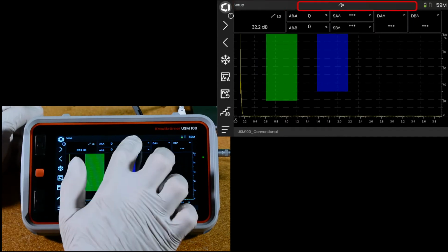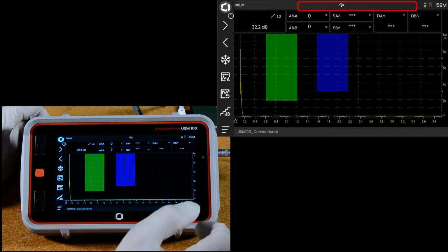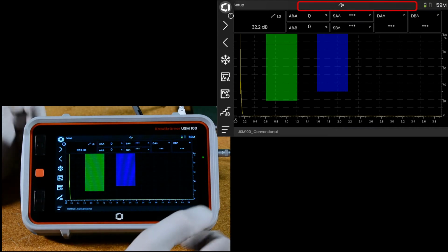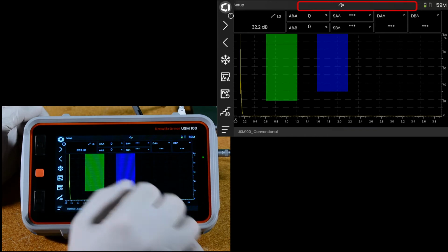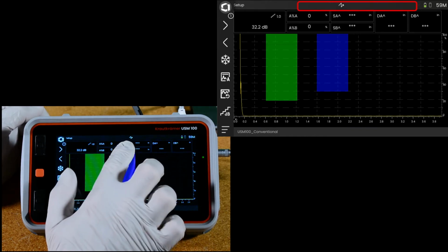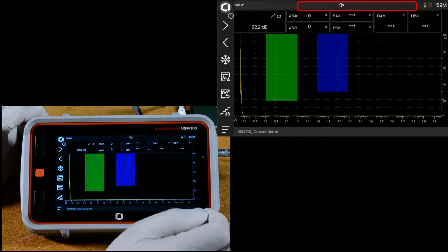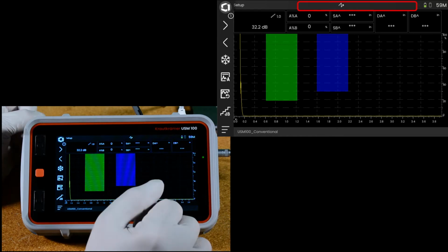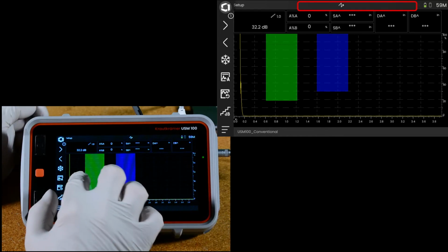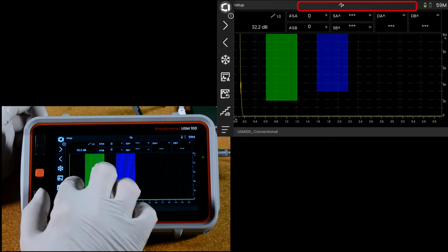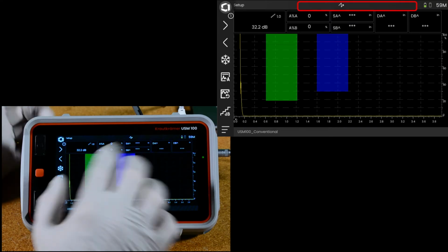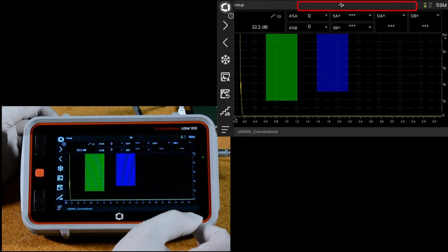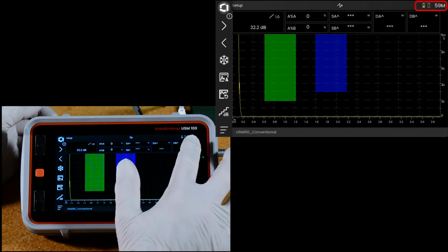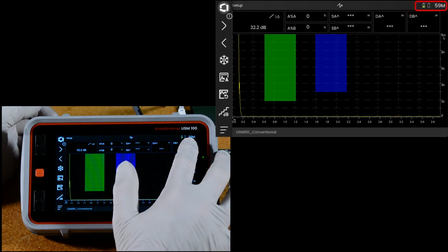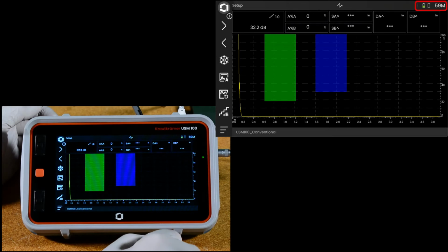Okay. Going across, there's an area for icons that indicate status or state within the instrument. We haven't done any calibration so far, so the only icon showing up there right at the moment is the icon that indicates I'm in pulse echo mode. If we were to go to the pulser receiver menu, turn dual mode on, that icon would change to indicate dual mode.